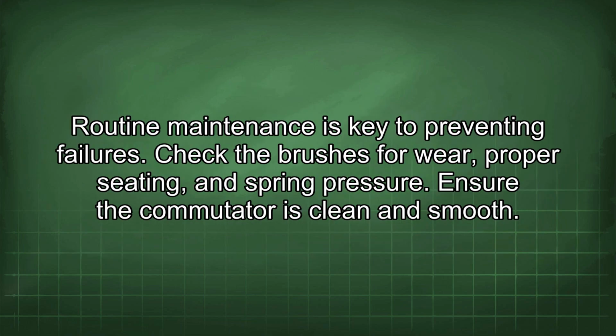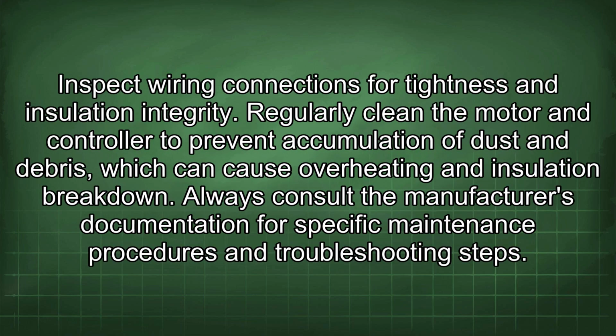Routine maintenance is key to preventing failures. Check the brushes for wear, proper seating, and spring pressure. Ensure the commutator is clean and smooth. Inspect wiring connections for tightness and insulation integrity. Regularly clean the motor and controller to prevent accumulation of dust and debris, which can cause overheating and insulation breakdown. Always consult the manufacturer's documentation for specific maintenance procedures and troubleshooting steps.